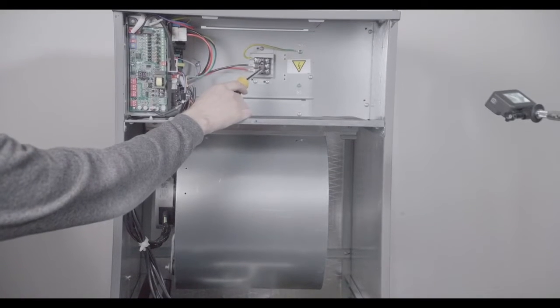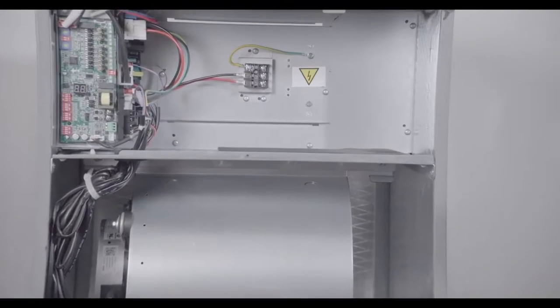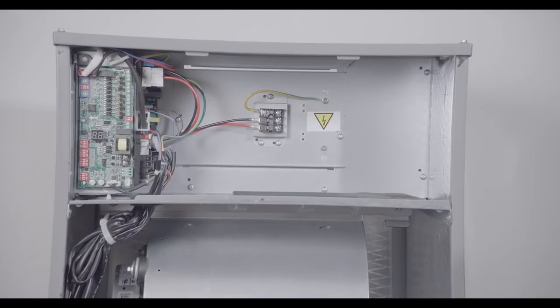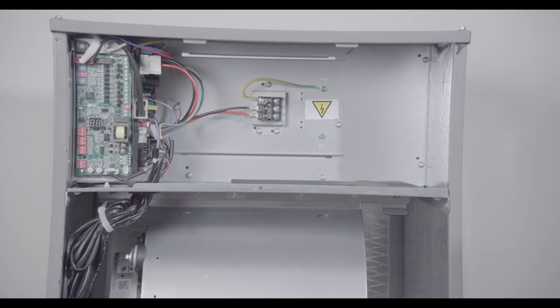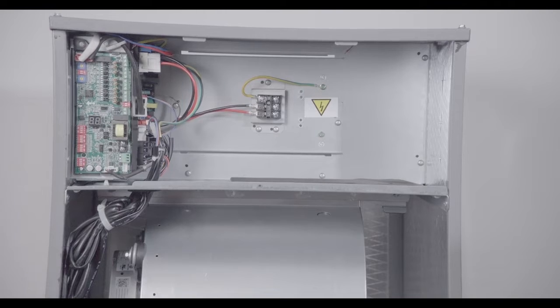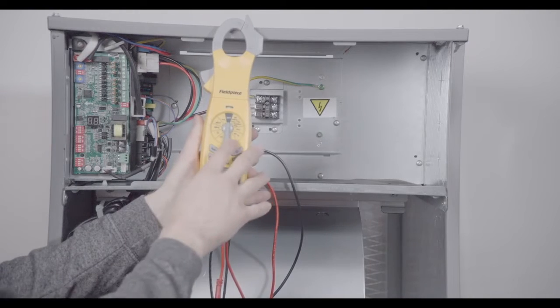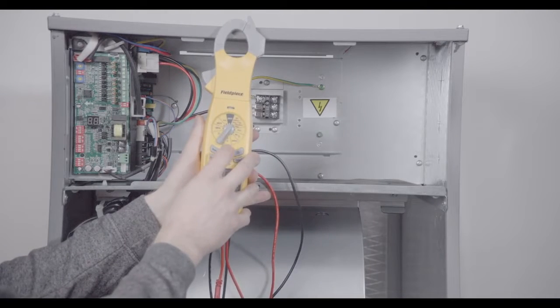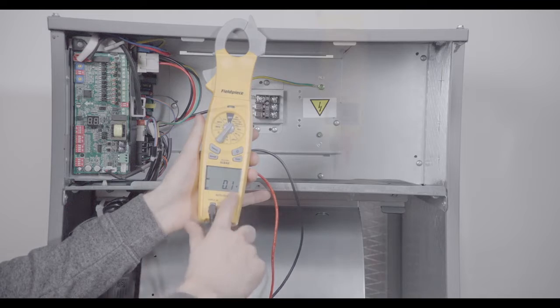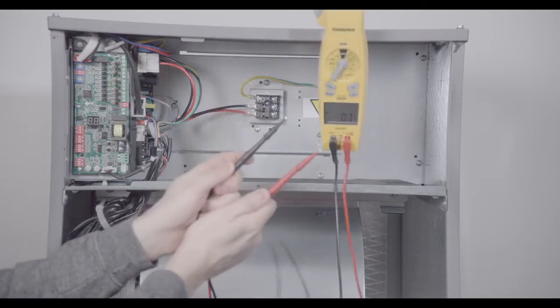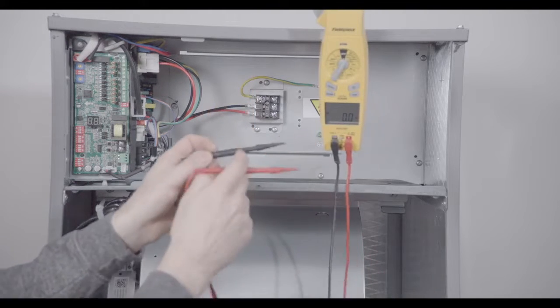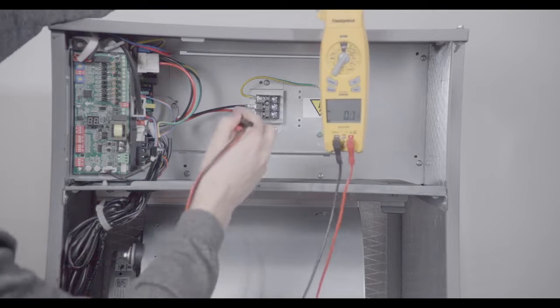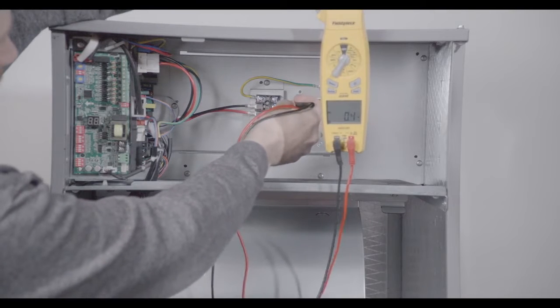Now, power comes in here at L1 and L2. In the field, the first step would be to test power. We set our meter to volts AC and we touch across L1 and L2 to verify there is no voltage present and it's safe to begin working on the unit.